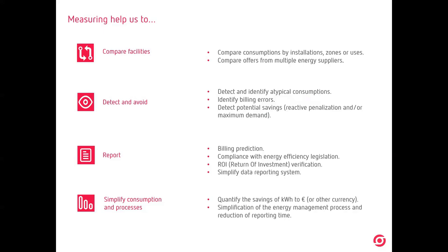Also, measuring is helping us to detect and avoid different things. Detect and identify atypical consumption. Well, there are some industries that don't know that during the weekend they are not producing, but they have consumption, for example. This is because they left the aircon or the heating system or the compressor or whatever connected. And they don't know until they start measuring. After installing analyzers, they will see how much energy they are consuming every day. Okay, so they will be able to identify if they are having any atypical consumption.